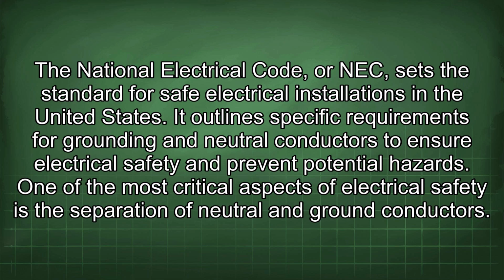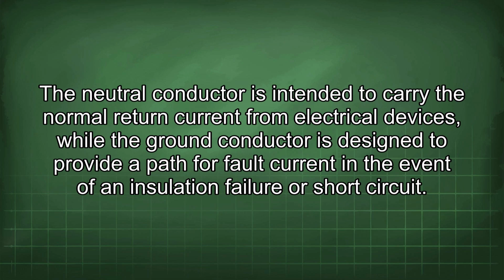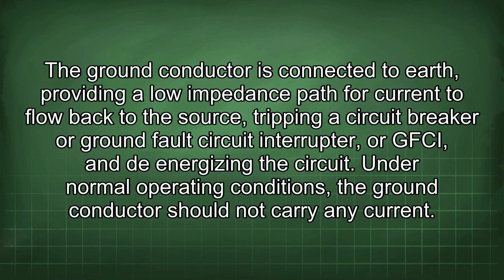One of the most critical aspects of electrical safety is the separation of neutral and ground conductors. The neutral conductor is intended to carry the normal return current from electrical devices, while the ground conductor is designed to provide a path for fault current in the event of an insulation failure or short circuit. The ground conductor is connected to earth, providing a low impedance path for current to flow back to the source, tripping a circuit breaker or ground fault circuit interrupter, or GFCI, and de-energizing the circuit.